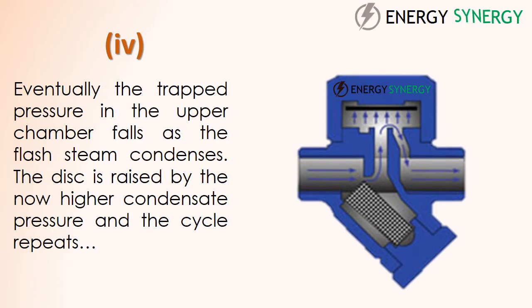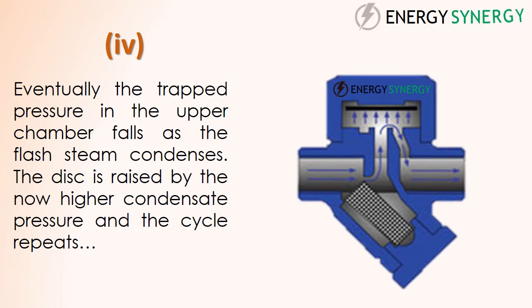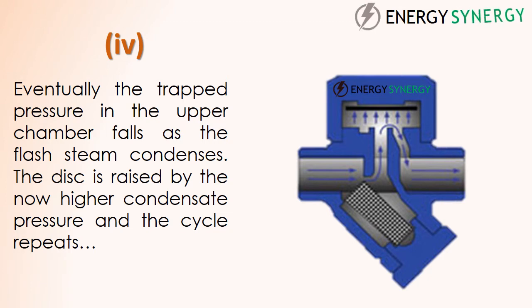Eventually the trapped pressure in the upper chamber falls as the flash steam condenses. The disc is then raised by the now higher condensate pressure, and the cycle repeats.